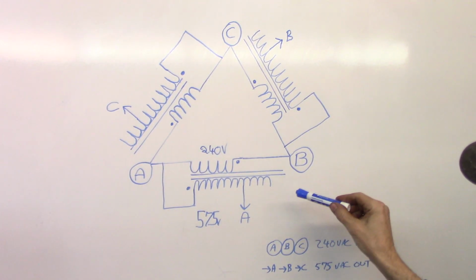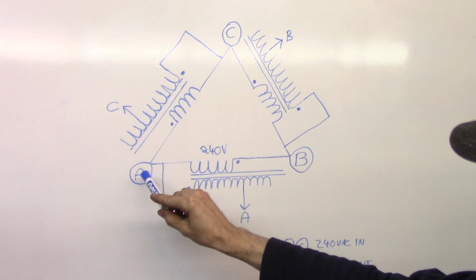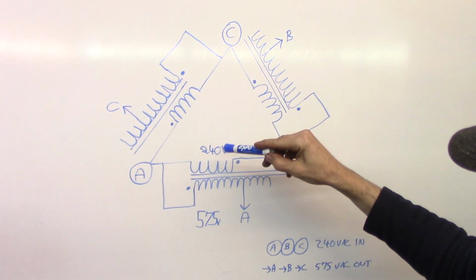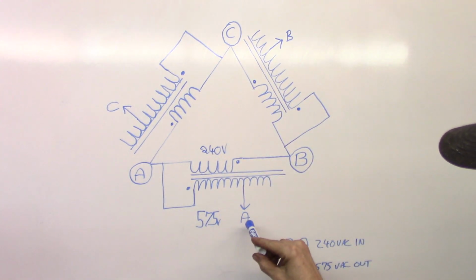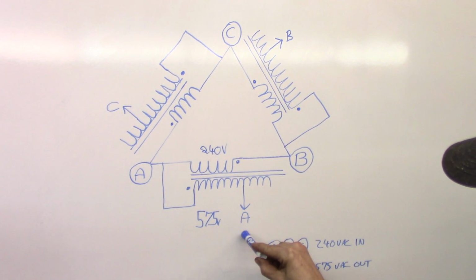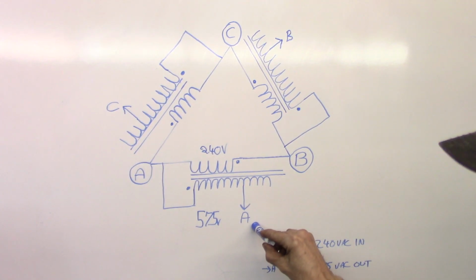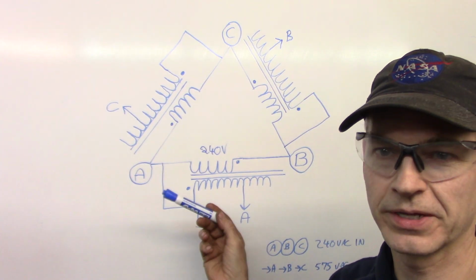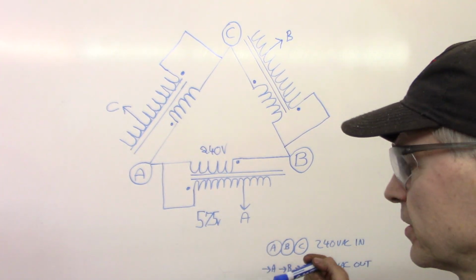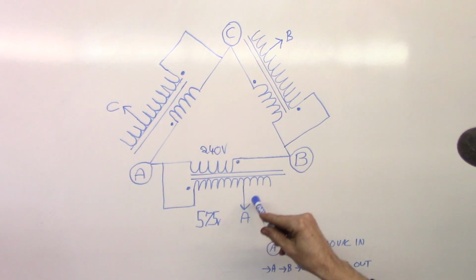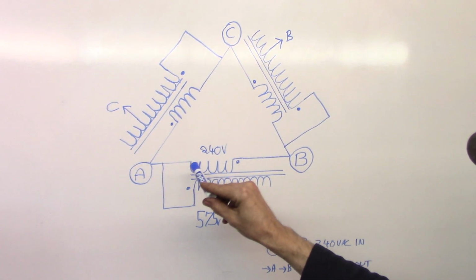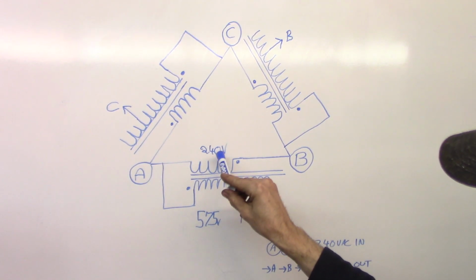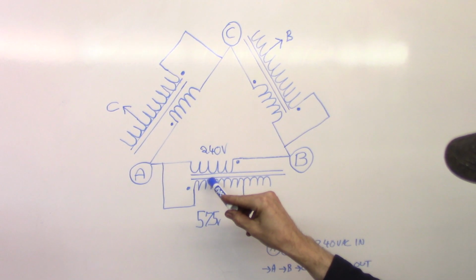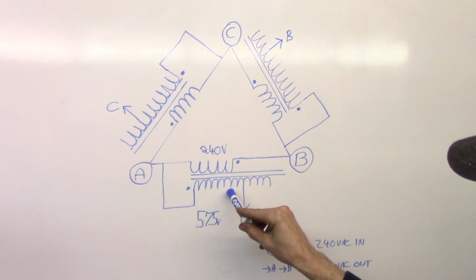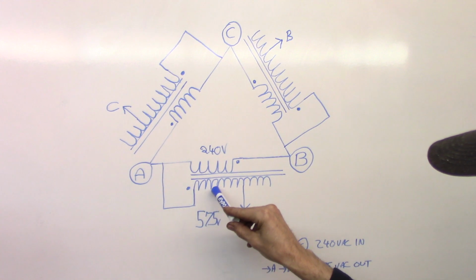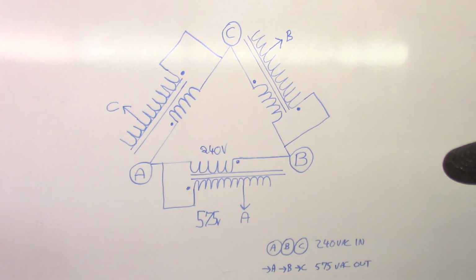So now, like I said, my current source is leg A, B, and C with phases existing between them. And the output is the arrow to A - that's the output, an arrow that looks like it's going outward. I didn't know how to label it, but this is coming out A. So you have the primary energizing the transformer, it's magnetically coming to the other coil here because that's what transformers do, and it's boosting it up, and because it's tapped, it's an auto transformer.